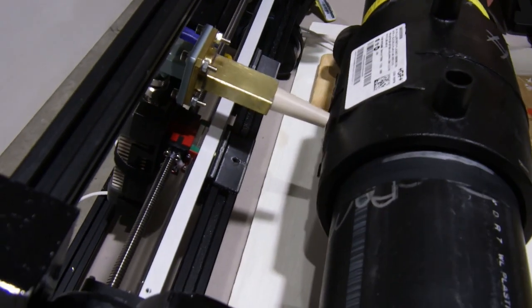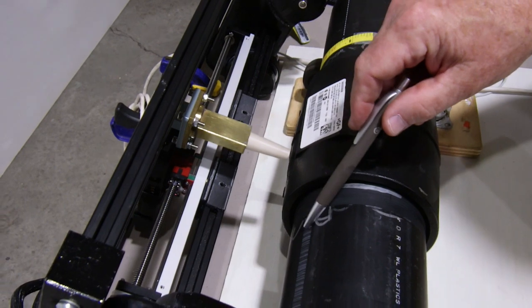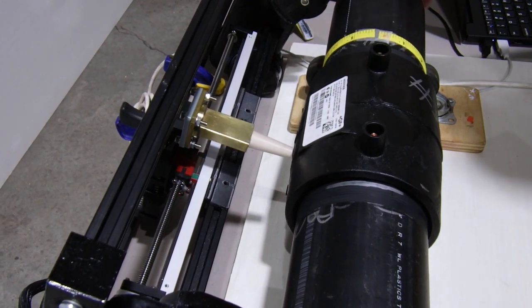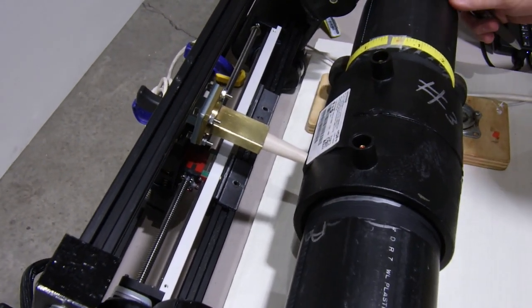Okay. Now what we need to do is take the antenna and place it on the left-hand side as our start point. Then essentially we'll scan across, we'll rotate the pipe, and we'll scan back across and continue the process until we finish scanning the pipe.